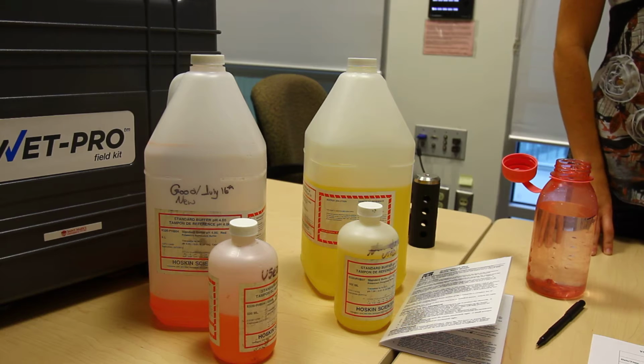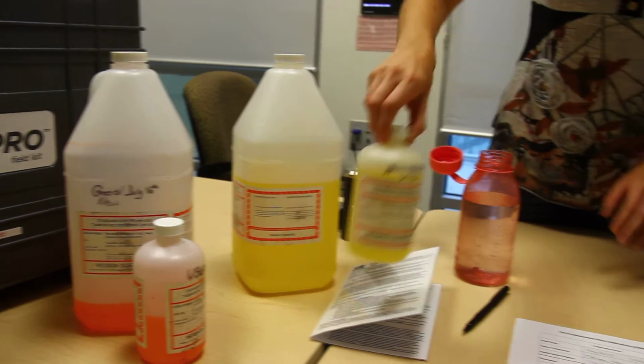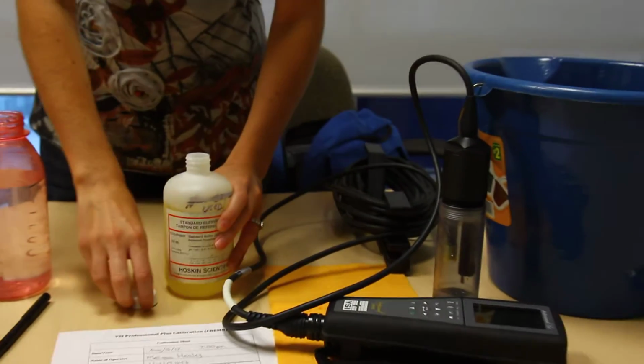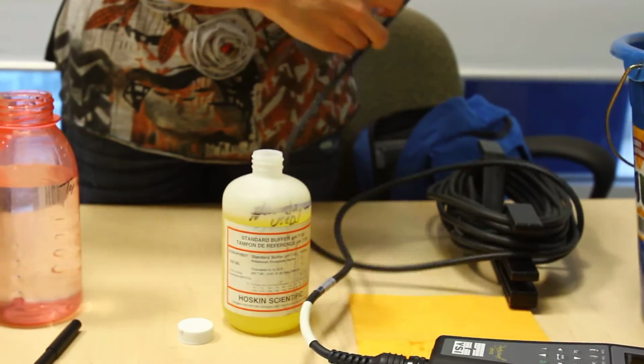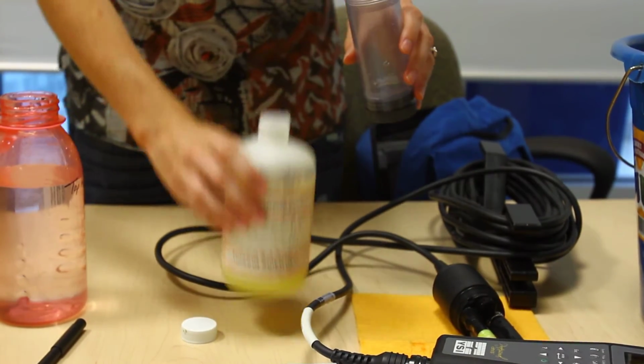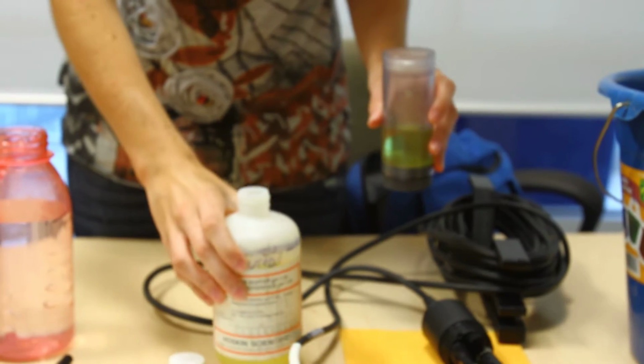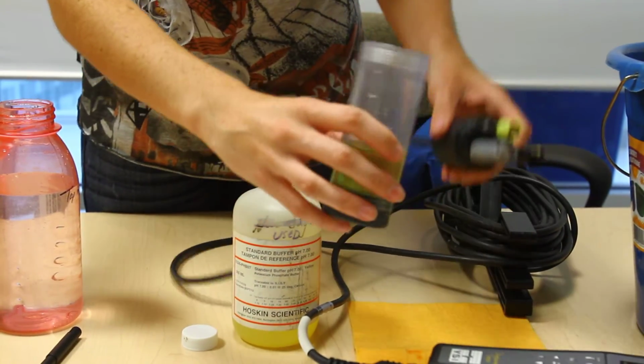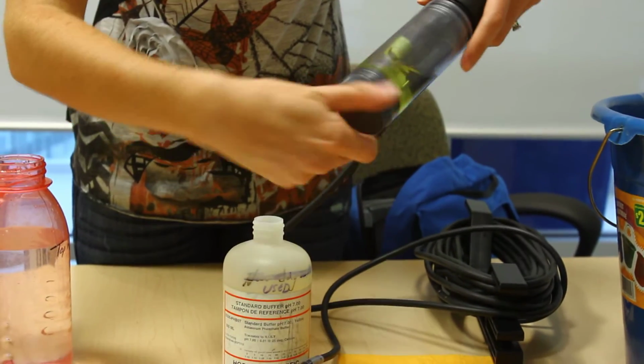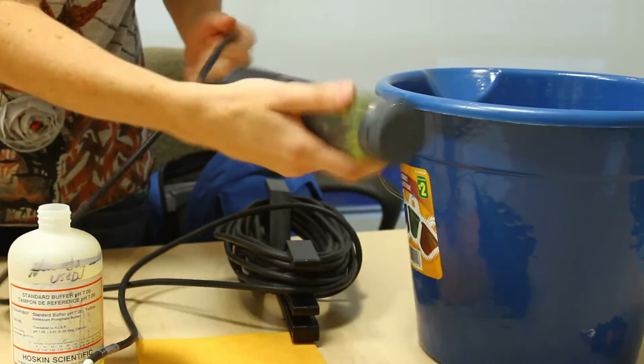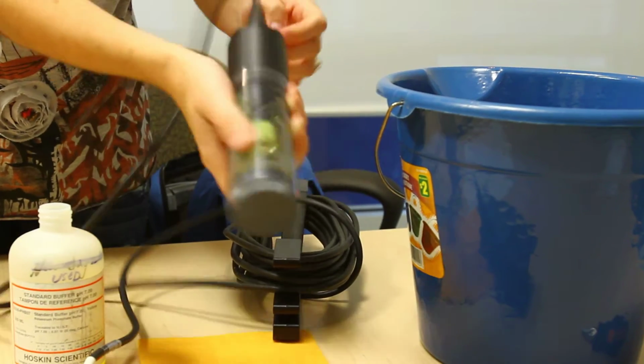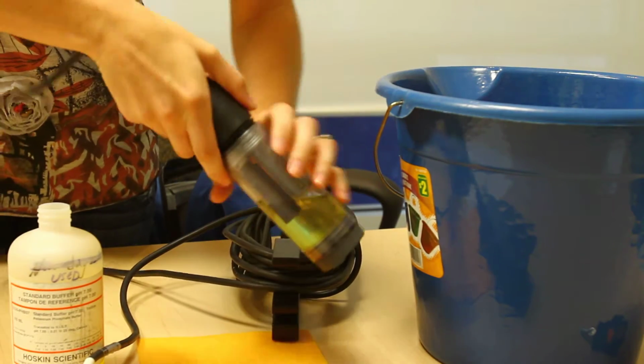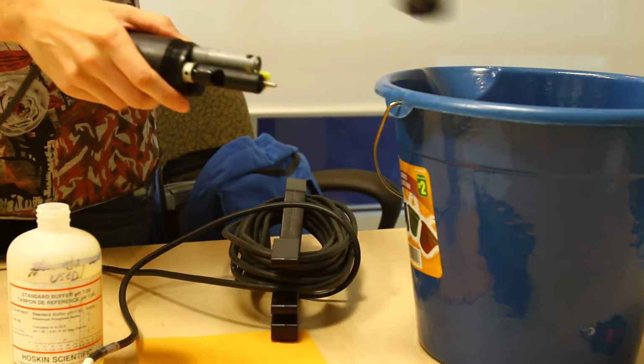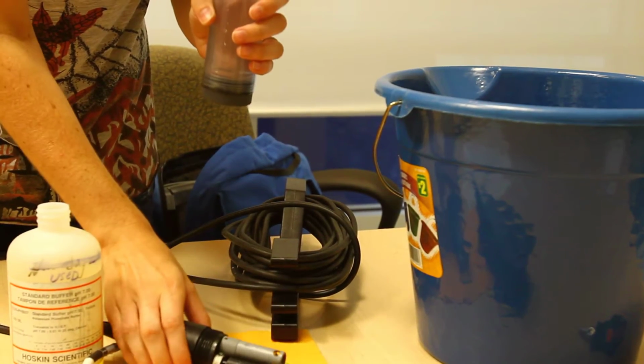We will begin with rinsing with used solution, and we will use pH 7. This is solution that has been used in past calibrations, and it's just for rinsing purposes. Pour a few inches of used solution into the bottle. Screw on the sonde and shake the solution around to rinse the bottle and the sonde. Unscrew the bottle and pour out the solution. Repeat this process once more with used solution.